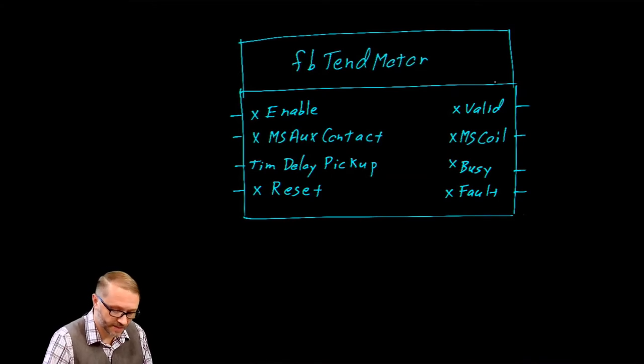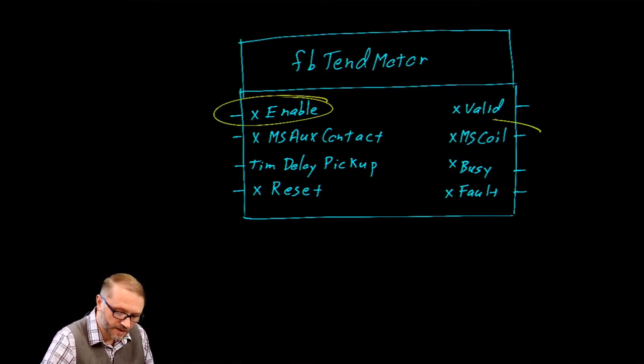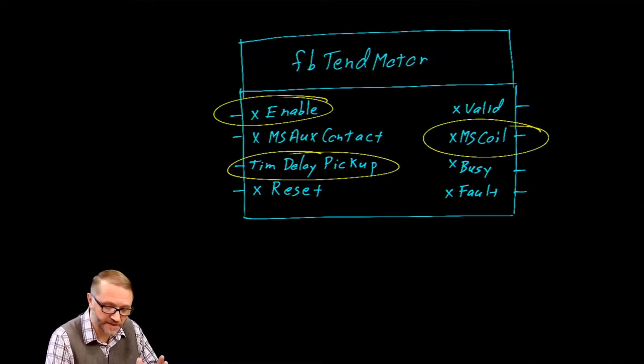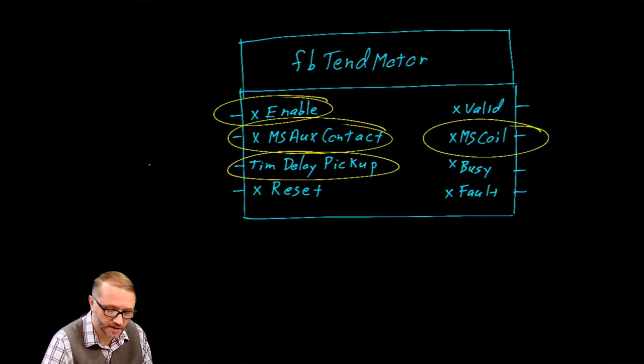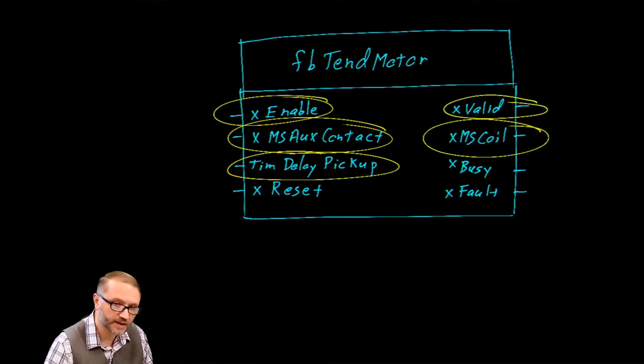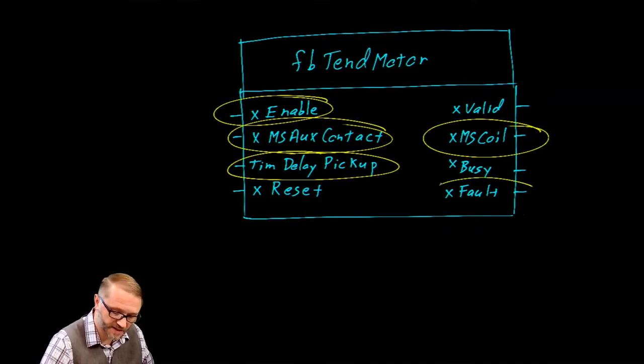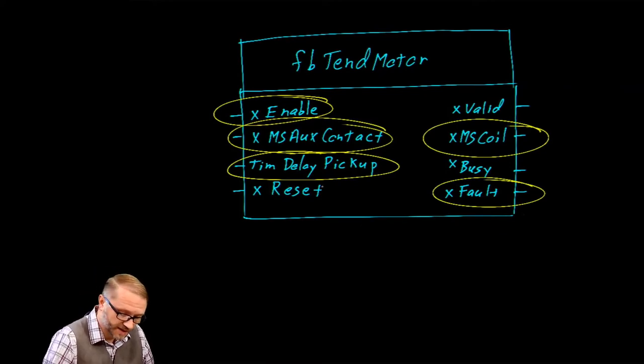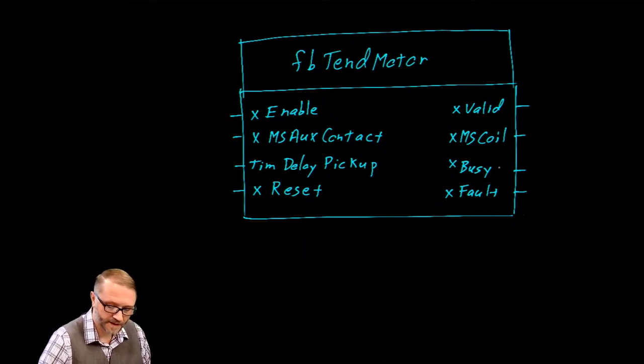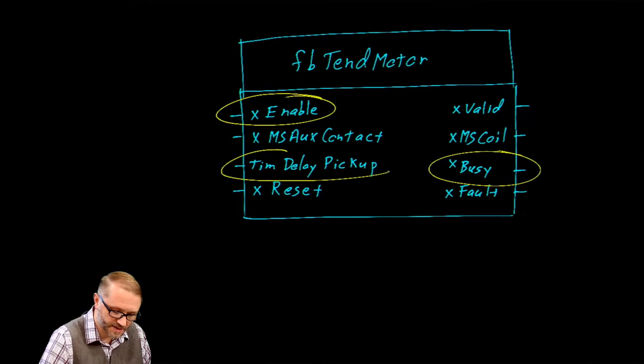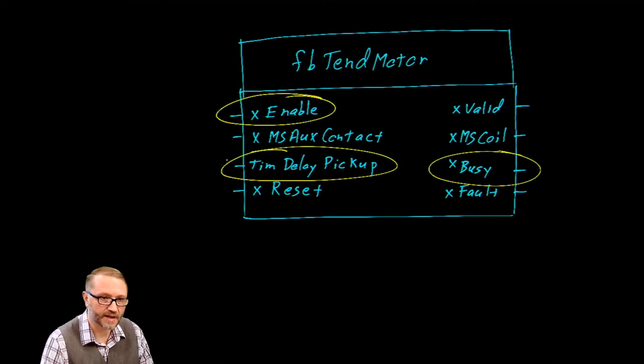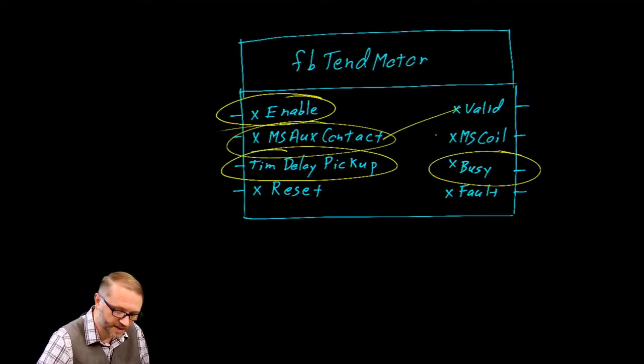This is the interface for that function block. If it's enabled, it will close the coil, activating the motor starter. After a time delay — because it takes time for the contact to physically close — it will monitor the auxiliary contact. If the auxiliary contact is closed, meaning the motor starter is active, the function block signals to the rest of the program that the motor starter is valid. If not valid, it signals a fault — actually, it latches into a fault position until reset. The busy output is only active briefly: when the block is enabled but has not yet timed out, signaling either valid or fault.